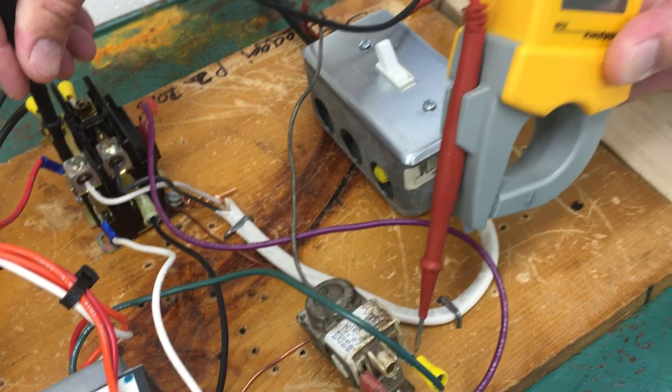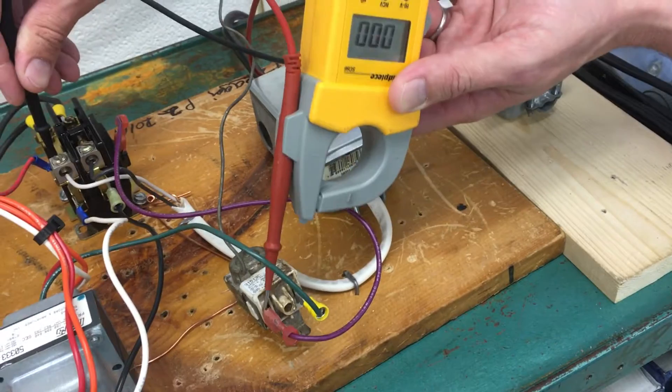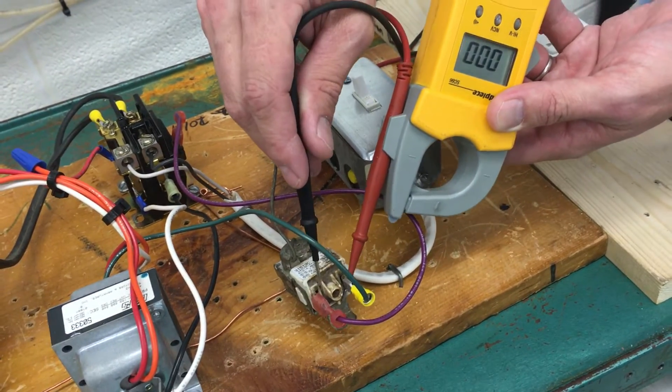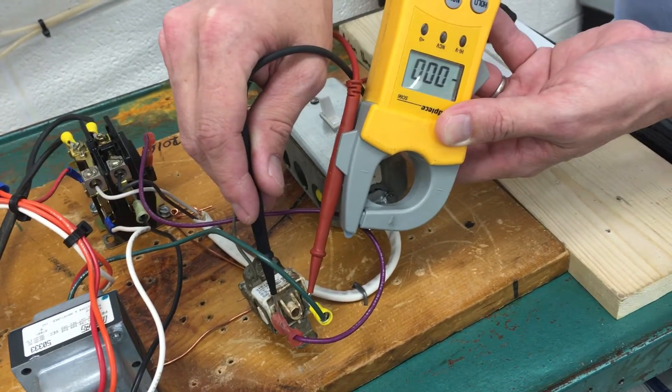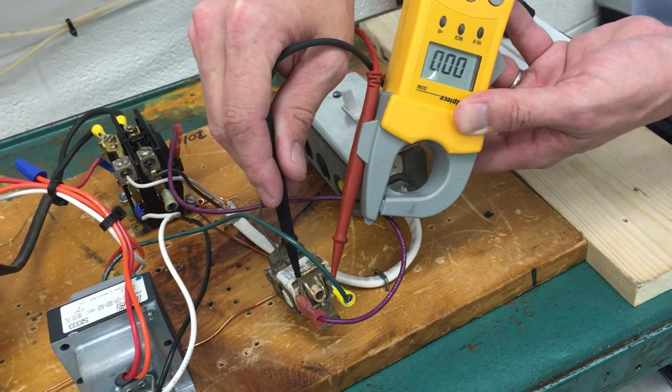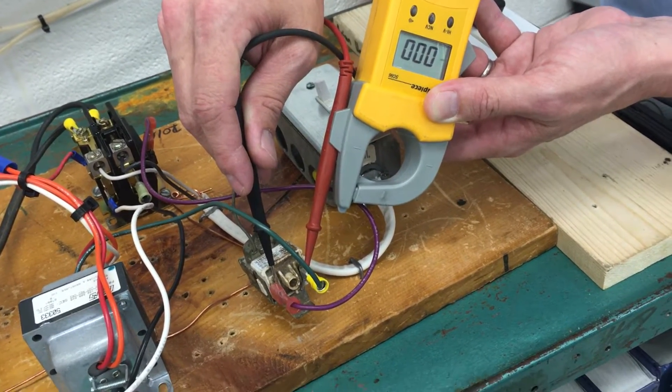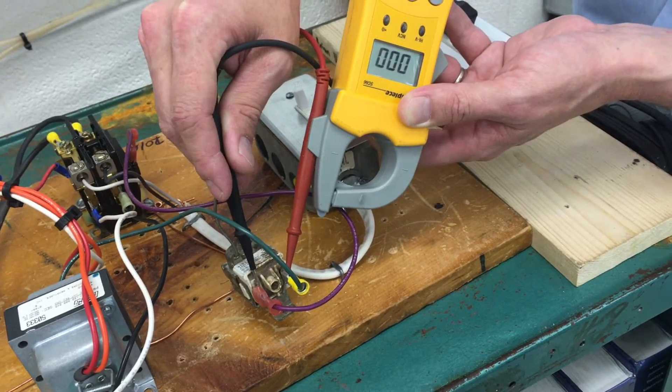Now I'm getting 24 volts because I've got a difference in potential, but if I measure both of them on the same leg with the thermostat energized, it'll show zero voltage. But again, that's not true. There really is 24 volts flowing through there, but I don't have a difference in potential.